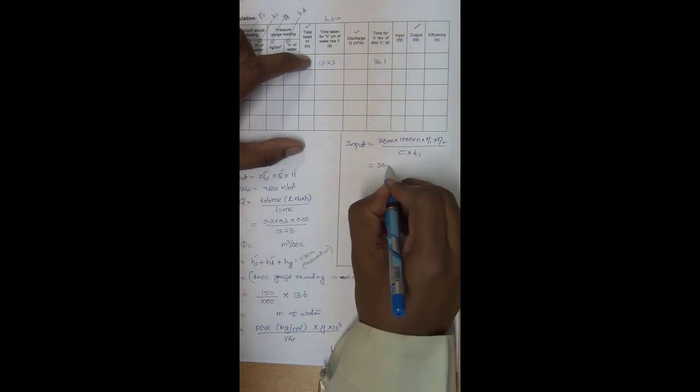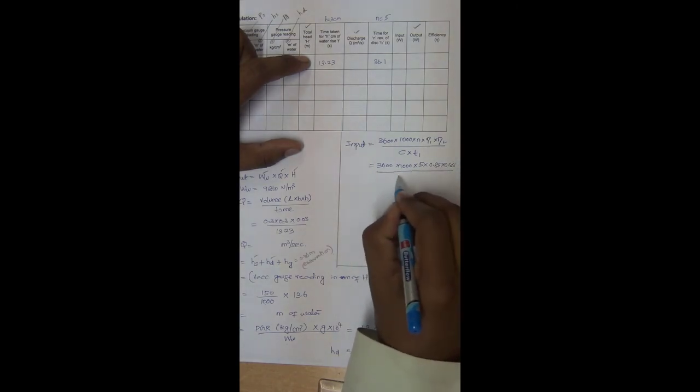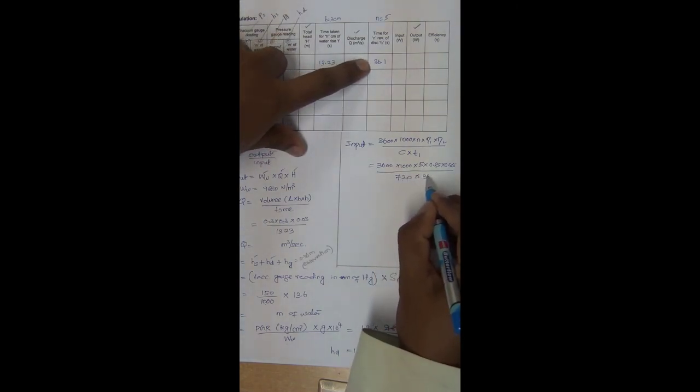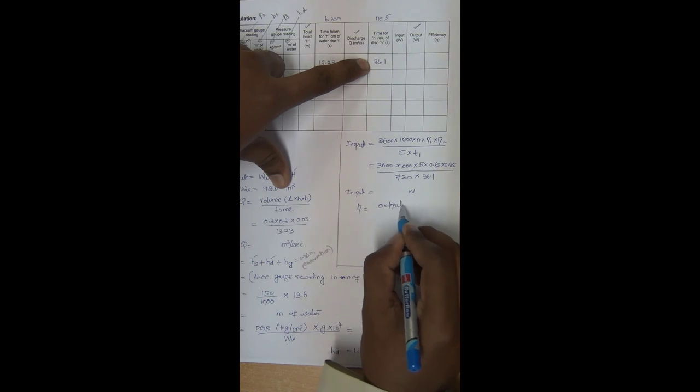To calculate input power, 3600 into 1000 into N into eta 1 into eta 2 divided by C into T1. So 3600 into 1000 into number of revolutions. Number of revolutions for reciprocating pump, let us assume it to be 5, into 0.85 divided by C is 720 into T1 is 36.1. We will get input power. Efficiency equal to output by input. We will get in terms of percentage efficiency.